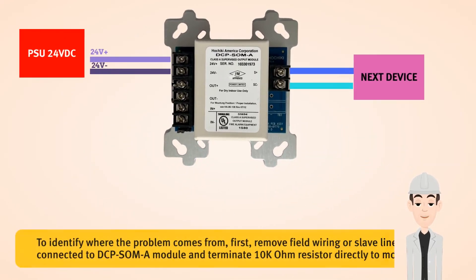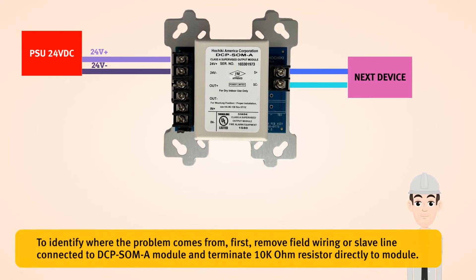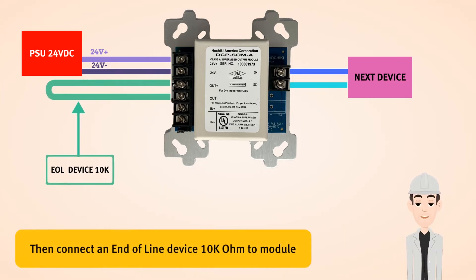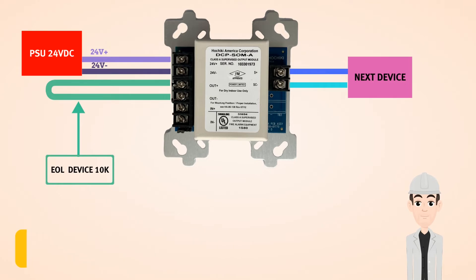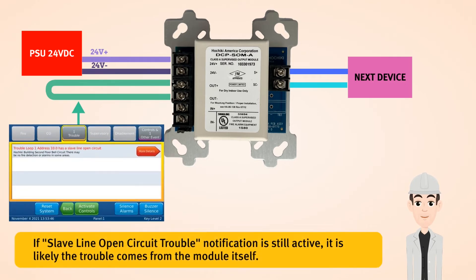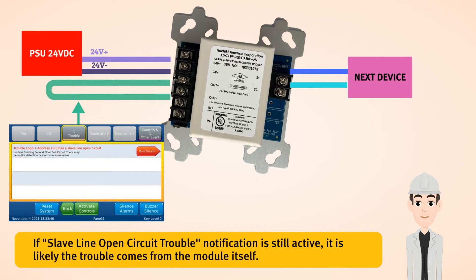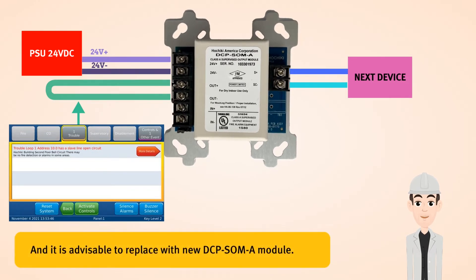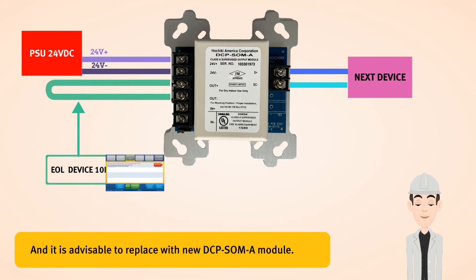To identify where the problem comes from, first remove the field wiring or slave line connected to the DCP SOMA module and terminate a 10k ohm resistor directly to the module. Then connect an end of line device of 10k ohm to the module. If the slave line open circuit trouble notification is still active, it is likely the trouble comes from the module itself, and it is advisable to replace it with a new DCP SOMA module.